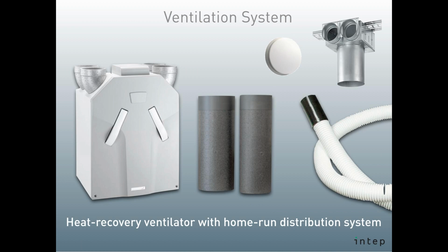So at the heart of it, on the left, we have the heat recovery ventilator. In this particular case, if anybody cares, it's a Zehnder Comfoair Novus 300 machine. And then the big pipes that come to and go to the outside in the middle are something called ISO duct or Comfo pipe, I think Zehnder calls it. It's insulation and duct in one, so you're not running duct and then trying to insulate it. It's actually made from EPS foam, so it just plugs into each other. It's a basic system and it's very bulletproof.